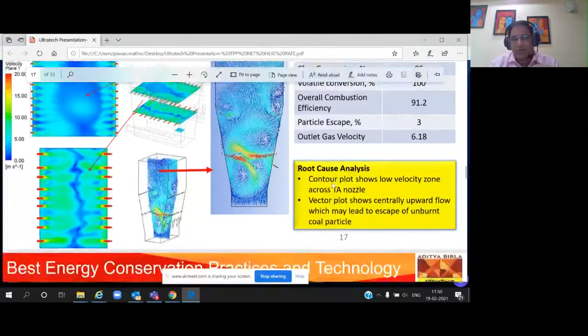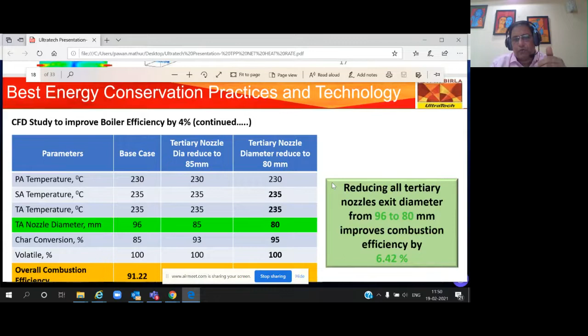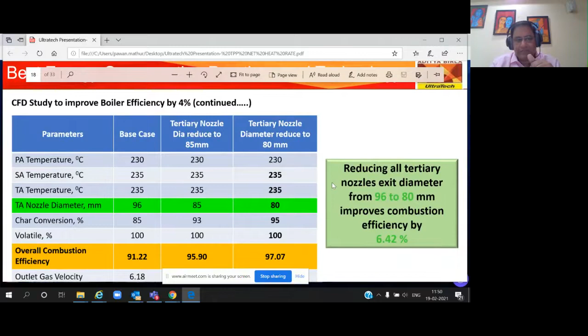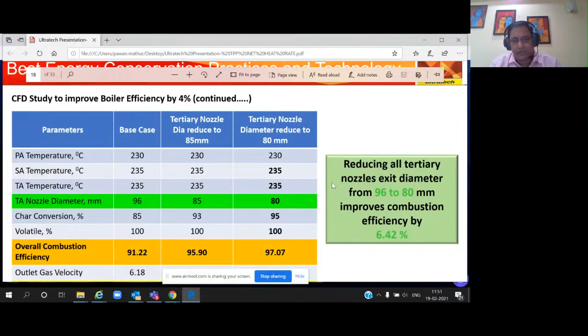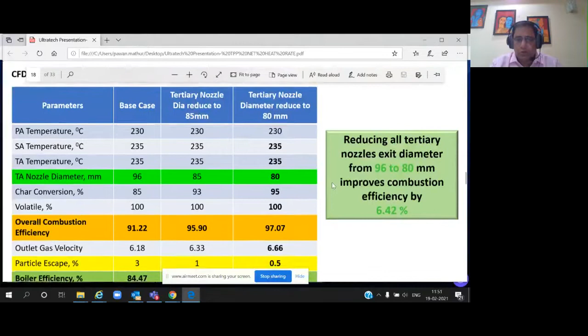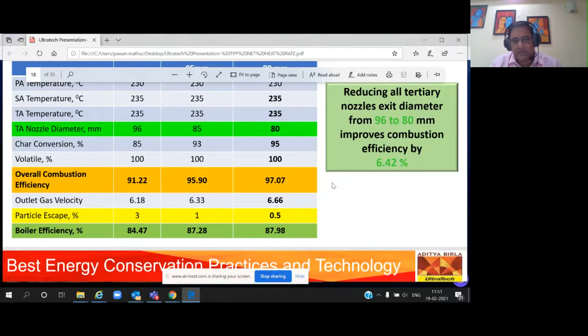CFD is a very good method to immediately improve efficiency in the range of 4 to 6, 7%, just by visualizing the process. For example, our tertiary air nozzle exit diameter was 96 mm. After CFD analysis, it was suggested that reducing this diameter to 85 or 80 mm could improve overall combustion efficiency from 91% to 97%, which would improve our overall boiler efficiency from 84.47% to around 88%. This was one example of CFD, and we have had many such cases that helped us improve efficiencies.